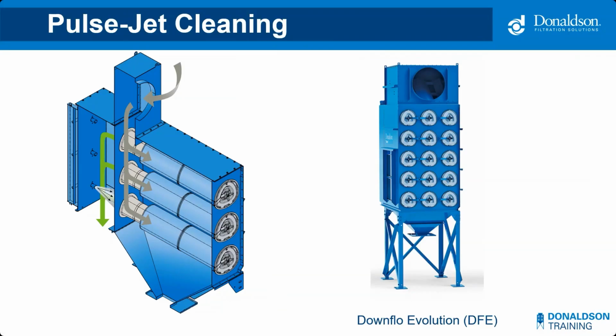An example of this pictured here is the DFE cartridge collector. The left image shows an interior view of the airflow. You can follow the gray arrows to see how the dirty air comes in from the top and follows a downward flow. It goes over the top of a set of venturis and the blue items, which are the filters that slide in. The air comes in, moves across the cartridge filter, and the dust or dirt in the airstream is deposited on the outside. The clean air follows the green arrow, moves through the filters, and exits through the bottom of the collector.